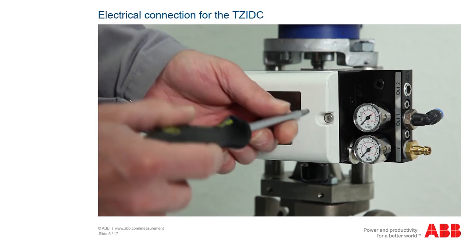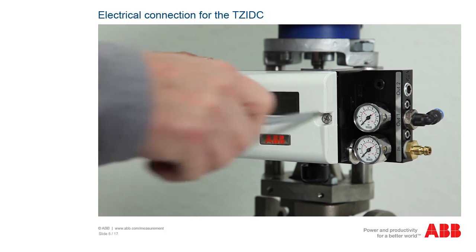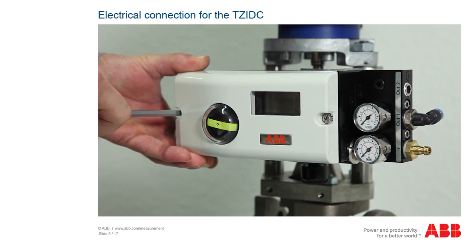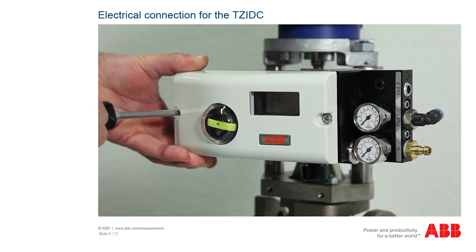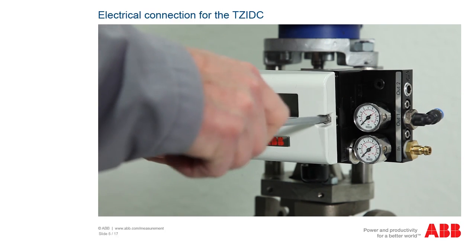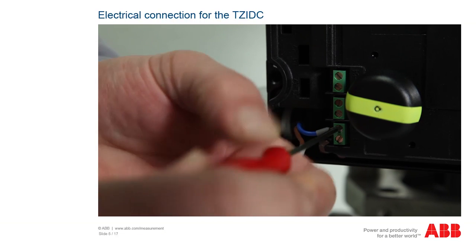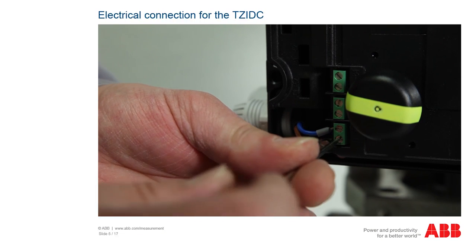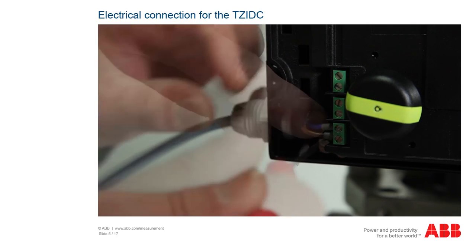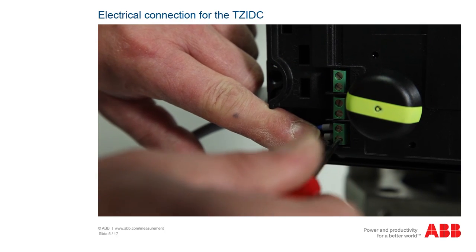The regulations for the electrical connection must be observed, as well as supplementary regulations for devices for potentially explosive atmospheres or in accordance with ATEX certification. The electricity must only be connected when the power is switched off. Open the positioner and pull the cable through the cable gland. Undo the compression fittings on terminals 11 and 12. Place the cable for plus on terminal 11 and the cable for minus on terminal 12 and tighten the fittings. For flexible cables, you should always use wire end ferrules.